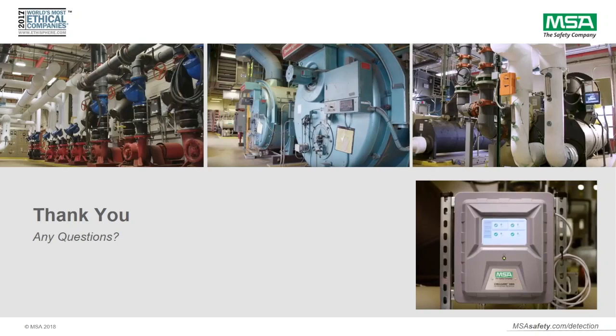How many relays does the monitor have? The Chillgard 5000 has a fault, caution, warning, alarm, and external horn relay, making that a total of 5. Let me remind everybody, if we don't get to your question, we will send answers out via email after the webinar. How many sample points can the monitor detect? The Chillgard 5000 can be configured for up to 16 sample points. The options are 4, 8, and 16 points. You can easily upgrade from 4 points to 8 or 16 just by ordering additional manifold assemblies.